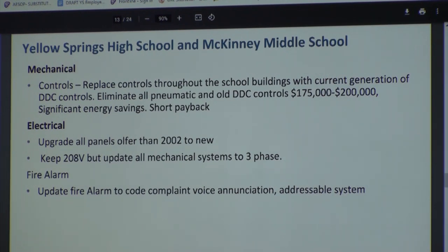If you do a renovation or a new building, the utility will come and say, can we change it to 480? Because we don't want to give you 208 anymore. We will, if we're your engineer, we're going to say yes. They give you the transformer, but then you have all new gear. That's the time to do it, if you're... they'll give you the transformer for free, they own it, they set it out there on the curb. You don't own your transformer, do you? I know the high school one, I'm thinking. Is yours?